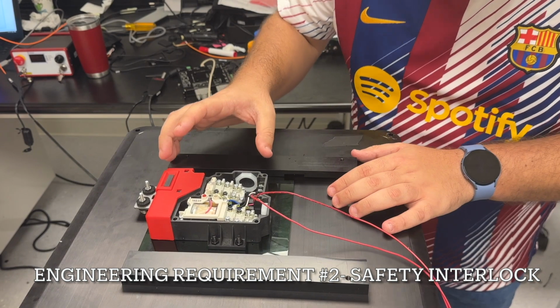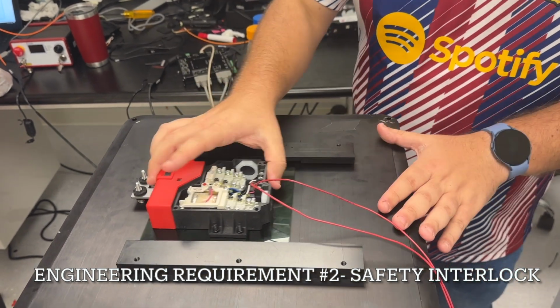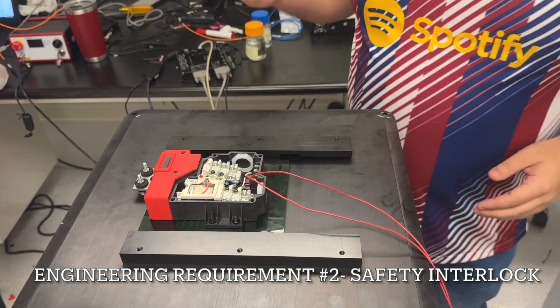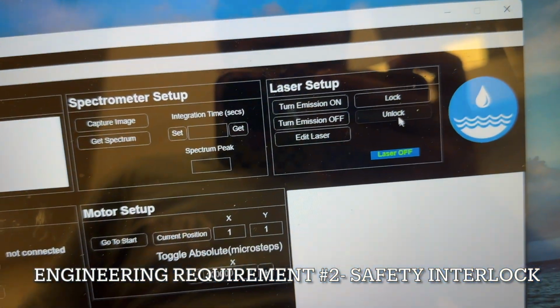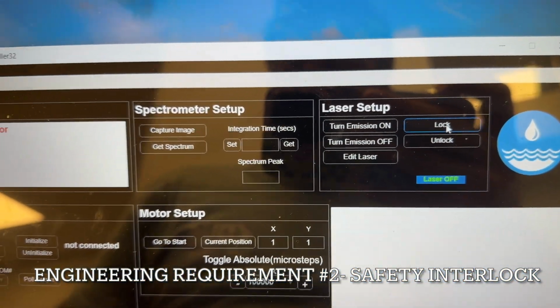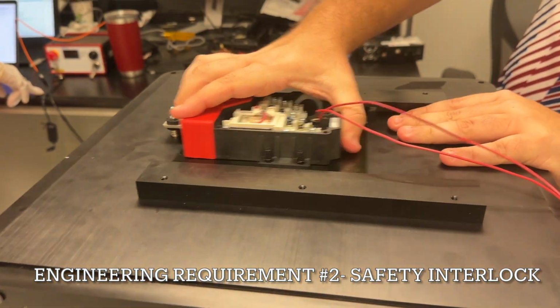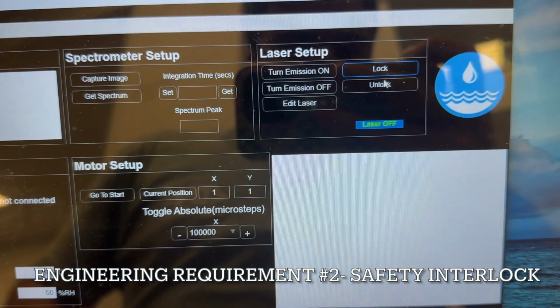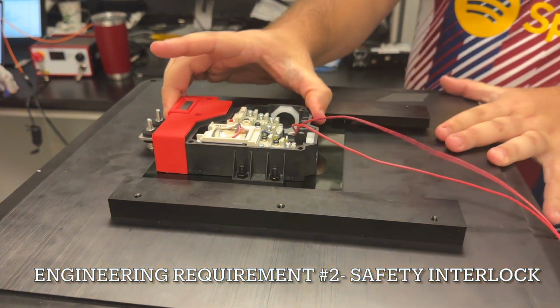Oh, hi. So today we're going to be demonstrating our safety interlock. As you can see right now, it's unlocked. And with the GUI right there, made by my friend Sebastian, we are able to unlock it and lock it at will. Right now it is in the lock position, so it is very difficult to open, with about 3,000 newtons of force required. And as he unlocks it now, we can see that it is now unlocked.